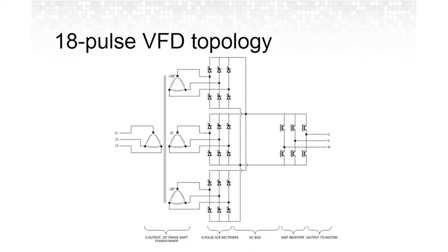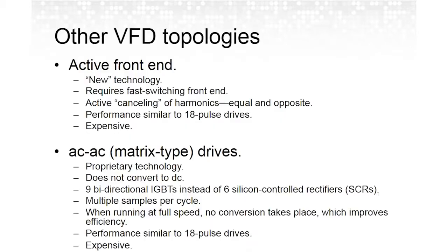This is incredibly effective in addressing harmonic distortion, but you can see from the basic diagram that you're dramatically increasing the complexity of the system and you're increasing the cost even more, where it's probably in the neighborhood of at least 50% more than a standard 12-pulse design. Typically, you would only see these in super large applications, say wastewater treatment plants and the like.